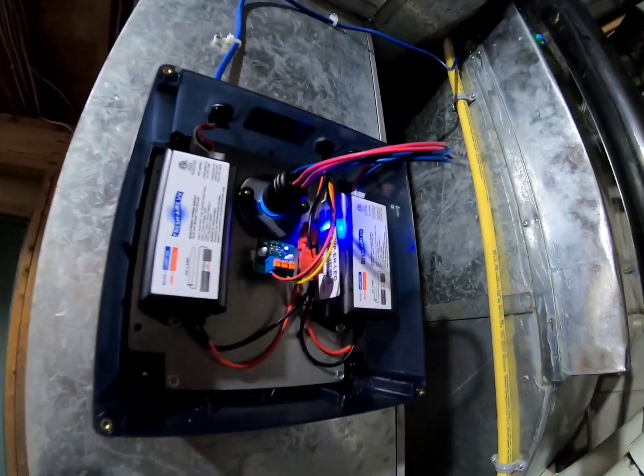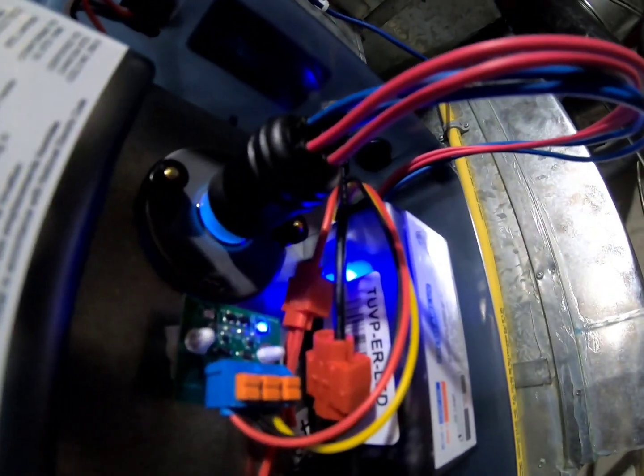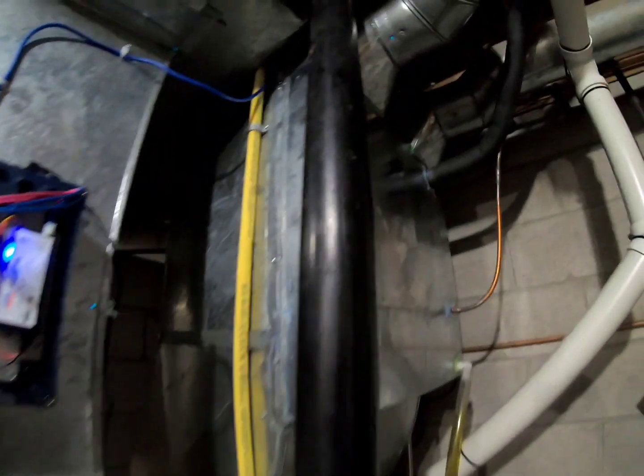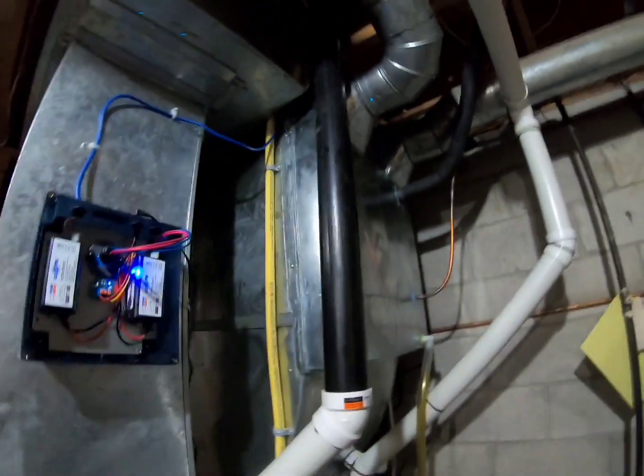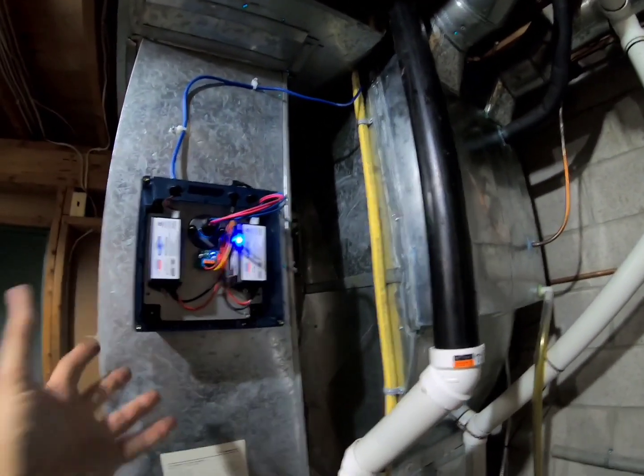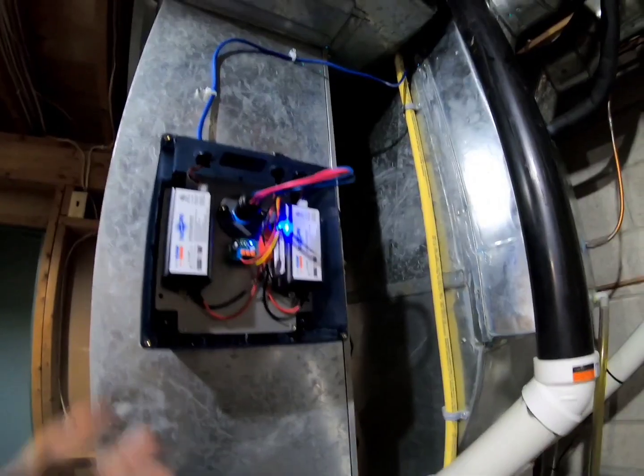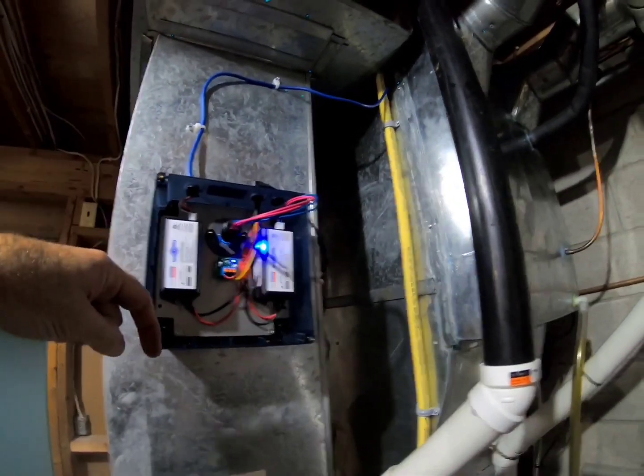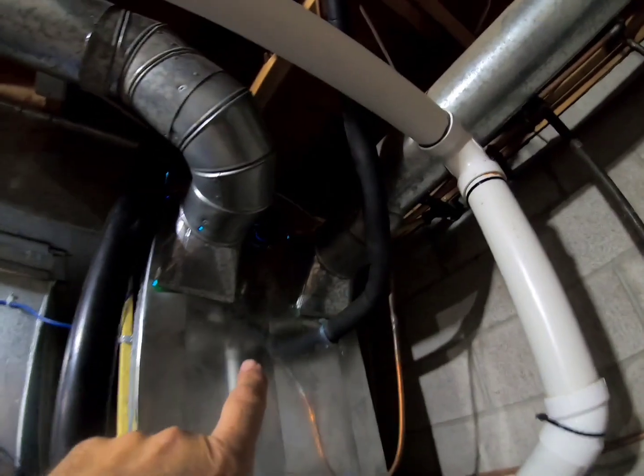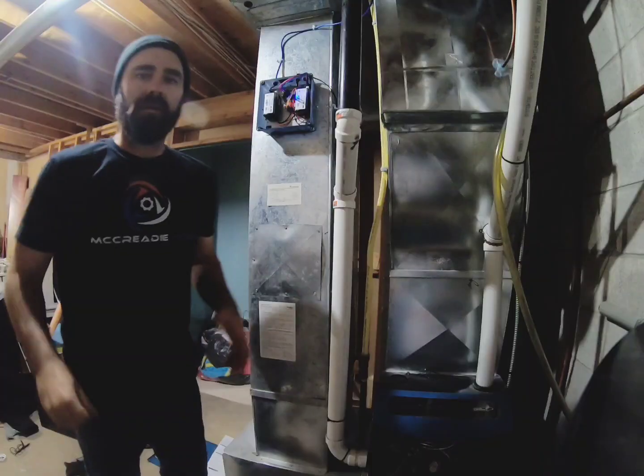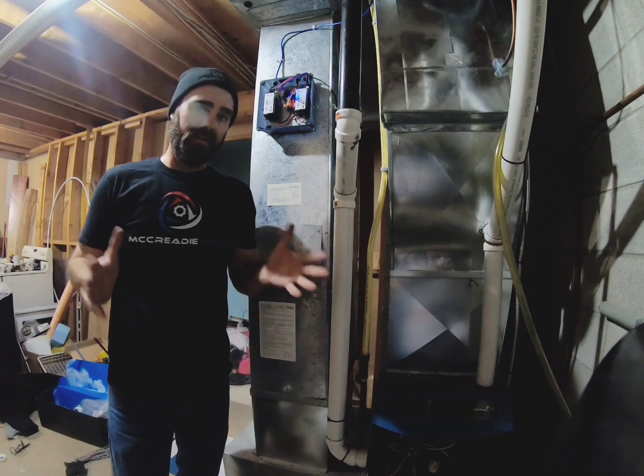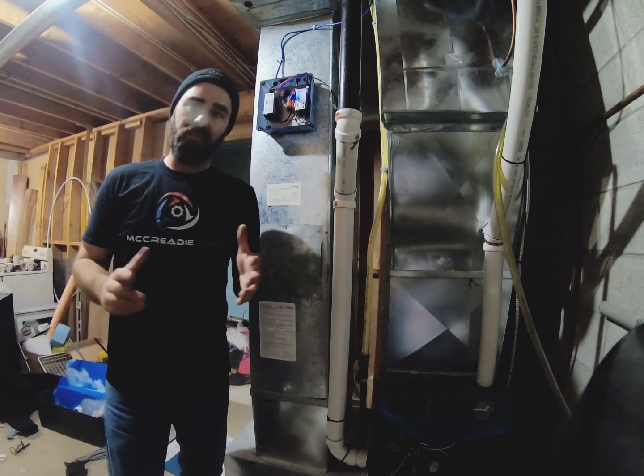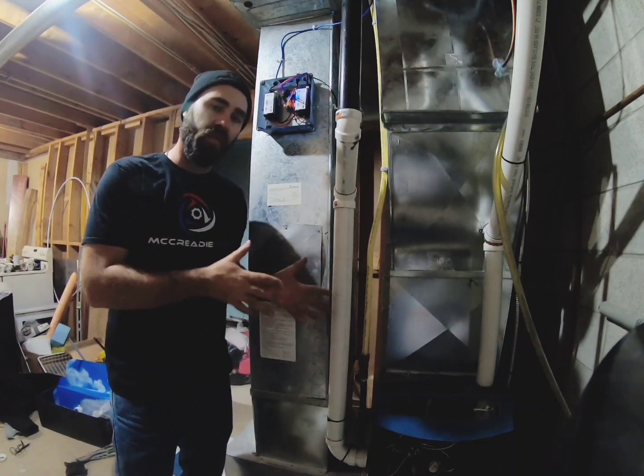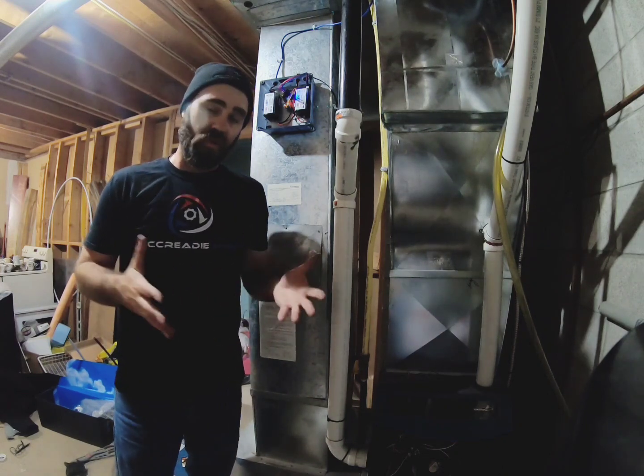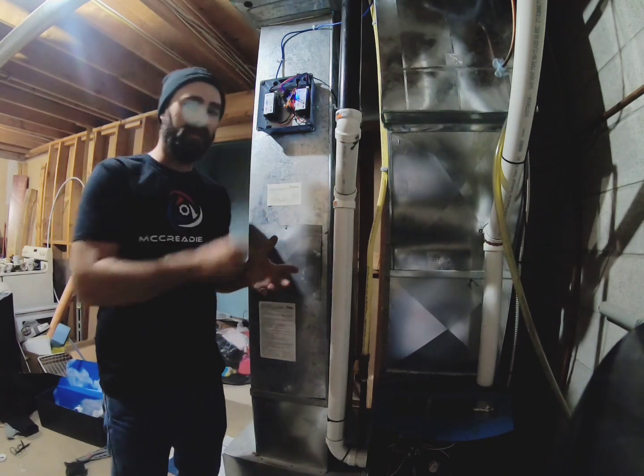So here we are all powered up, and we can see the faint glow of the UV bulb in the return, and then up at the supply we can see the same thing. So we've just installed an APCO-X system with a UV light in the return and the carbon matrix with the UV bulb first and then the matrix, and then we have the remote UV bulb to disinfect the coil right above. So all in all, very, very simple installation. Just make sure that you read the manual and make sure that you use a secondary transformer and not the one that comes with the furnace, because you don't want to short it out by drawing too much amperage through the APCO-X.